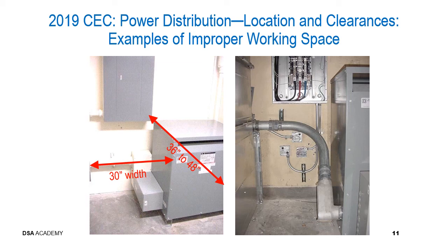These two photographs depict a couple of examples of improper working space provided in front of distribution panels. On the photograph on the left, we're basically reiterating that the clear depth required in front of a panel is generally 36 inches to 48 inches, and also, the required minimum working width in front of a panel is 30 inches. Now the problem that you can see in this particular photo is that that small gutter on the bottom near where a serviceman's feet would be, that looks like it's connected to a transformer, certainly extends out further than 6 inches in front of the panel. So that's what makes that an improper working space.